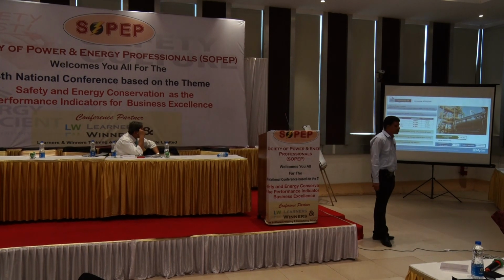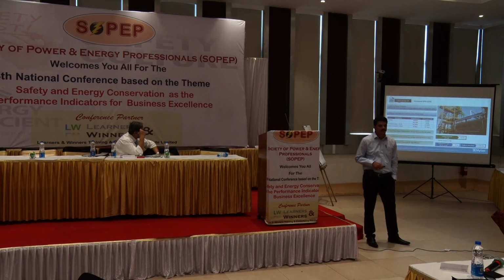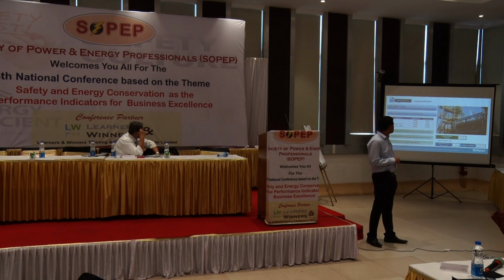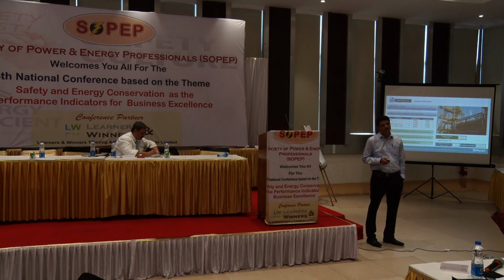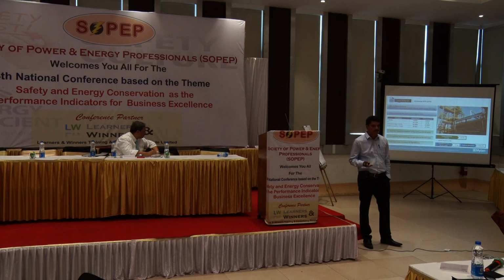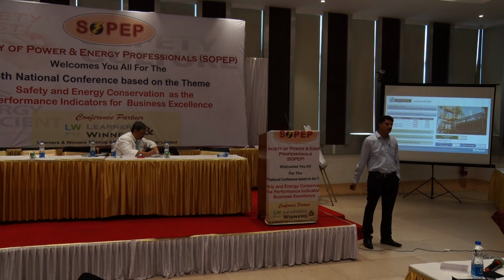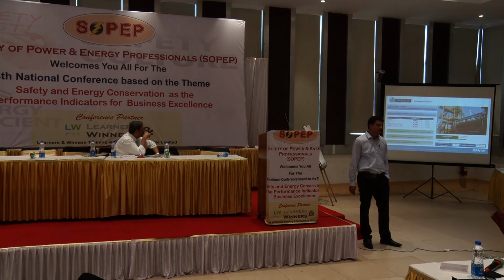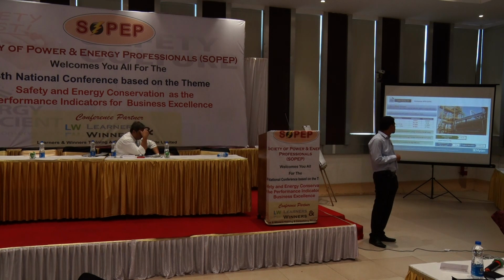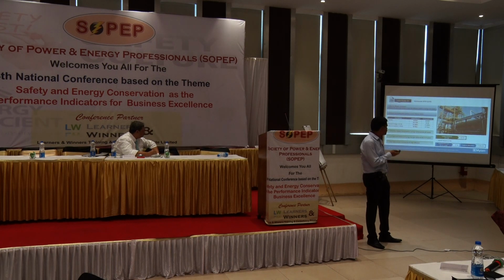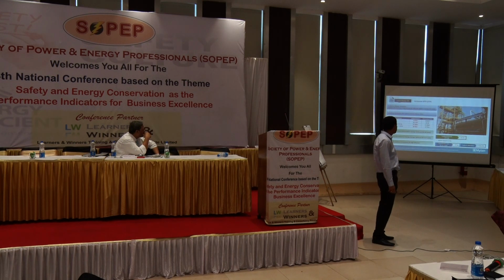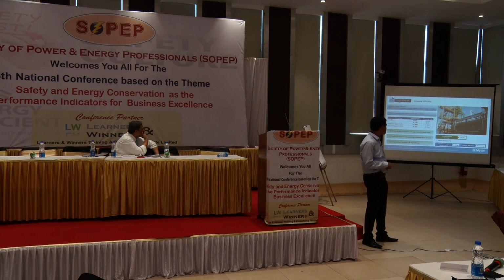One of our processes generates effluent with 32% solids. To treat that effluent, we used conventional reactors for forced evaporation. We were taking the effluent into the reactor and applying steam. It would be evaporated into the environment, and there is a lot of pollution. To overcome that, we have installed a horizontal ATFD and we have taken out those 5 reactors. Those reactors we have utilized in the process, and this is high efficiency. This will consume less steam and thermal energy and less electrical energy. The investment is 97 lakhs, payback is 14 months. The total savings are 69 lakhs.